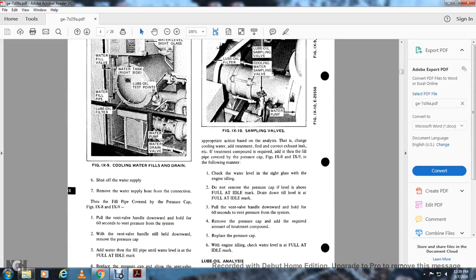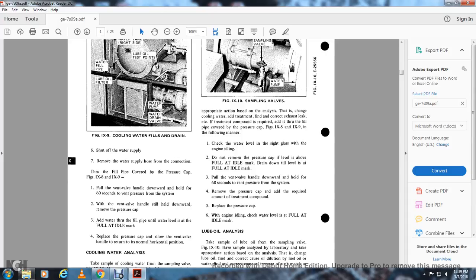Check the water level and cycle after the engine is at idle. Do not remove the pressure cap if the level is at the full idle mark. If above the full idle mark, drain down until the level is at the full idle mark. Pull the vent valve handle down for 60 seconds to vent pressure from the system, then remove the pressure cap and add the required amount of treatment compound. Replace the pressure cap and, with the engine at idle, check the water level at the full idle mark.